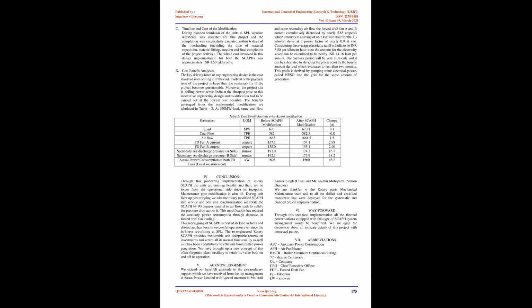SCAPH coil bank loading and rotating arrangement. The individual weight of coil bank is 298 kg, which was acting vertically downward, and the bearing should be capable to bear this axial loading. Therefore, thrust ball bearing was suitable for loading and rotating purpose. For loading of SCAPH coils, a hole of diameter of 110 mm was made in the channel to insert the shaft, which was to be loaded on the thrust ball bearing along with bearing base plate, which finally takes the load of coil with the help of tie rod, which was welded with the spool piece.